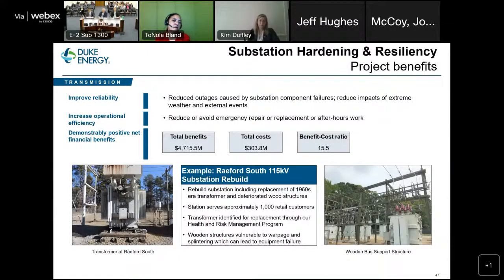A specific example for substation hardening and resiliency is our Raeford South 115 kV substation rebuild. You can see on the lower right what these wooden structures look like supporting equipment, and on the left is the transformer at Raeford South that we're targeting for upgrade. I'll talk more about transformer upgrades and their drivers shortly. This involves rebuilding the substation, replacing equipment that is at end of life and at risk of failure, to prevent future impacts to our customers, eliminating wooden structures and upgrading everything to steel structures designed to the latest standards. This is a smaller station serving approximately 1,000 retail customers, but still important for our retail customers in the Raeford, North Carolina area.